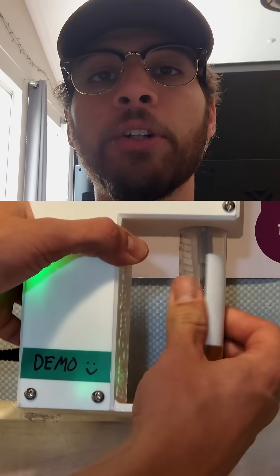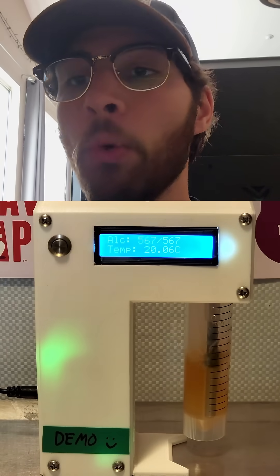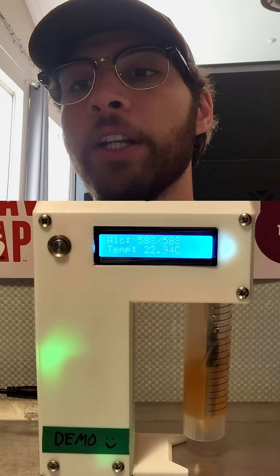As we screw in a sample here, air blows into the kombucha and the readings at the top of the display will rise. This machine was calibrated at 23 degrees Celsius, so we need to be within one degree Celsius of that reading.